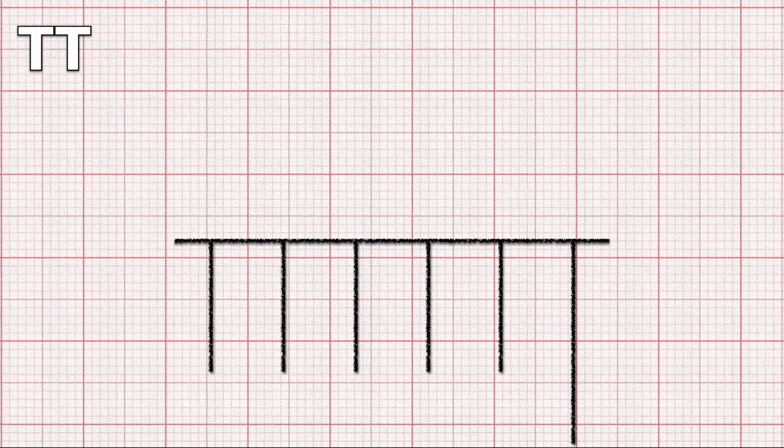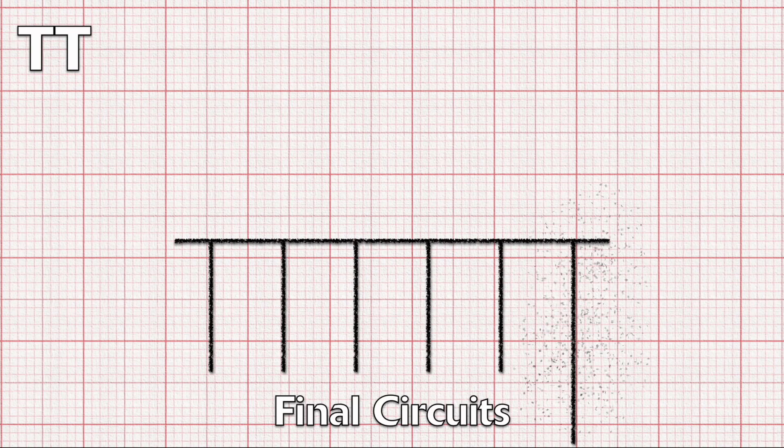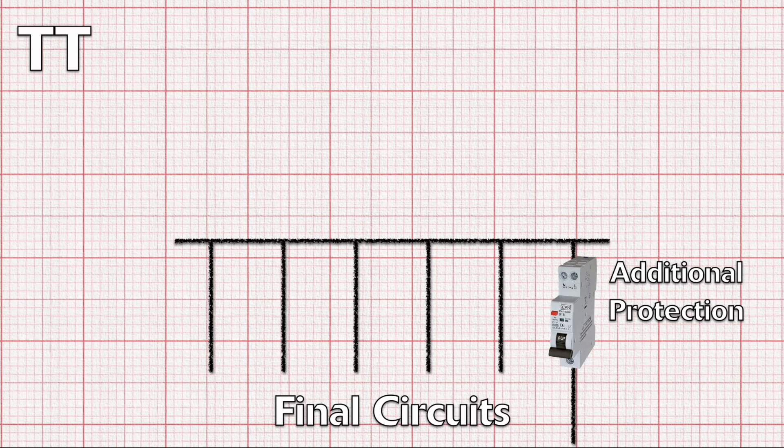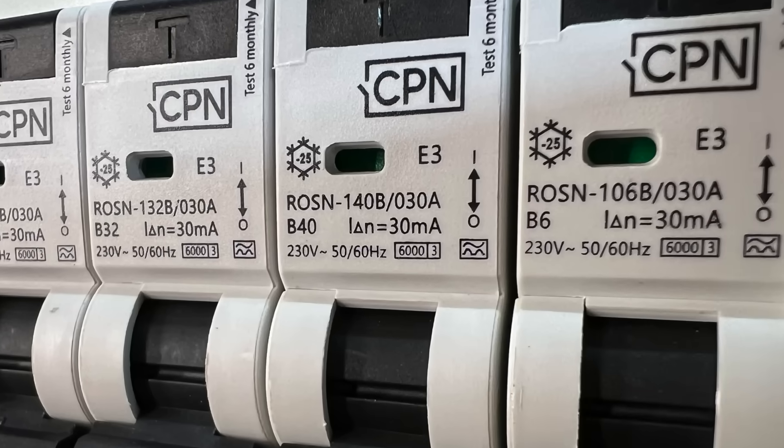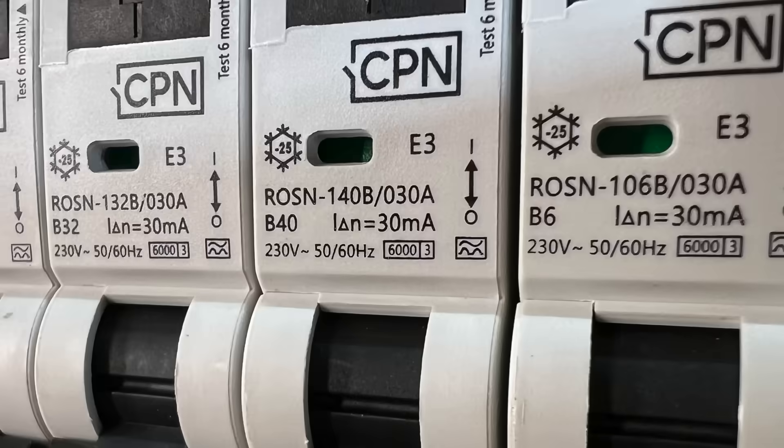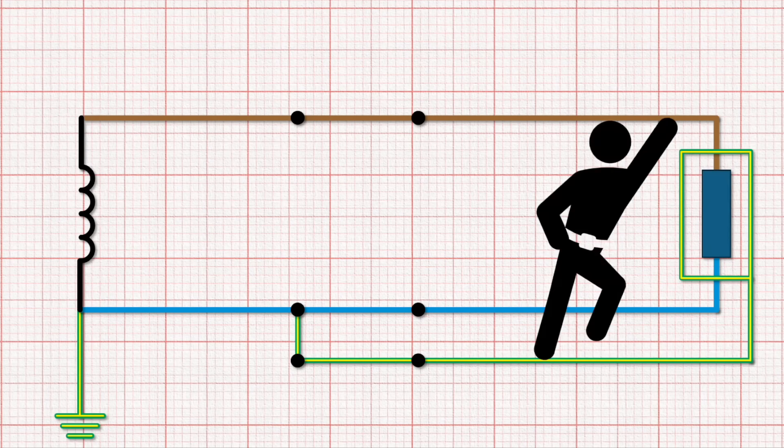So let's say you're protecting a final circuit in a TT system. For the reasons outlined earlier you'll probably need to use an RCD for additional protection. And so an RCBO rated at 30 milliamps will disconnect overload, short circuit and high impedance earth faults either through the wiring system or a person.